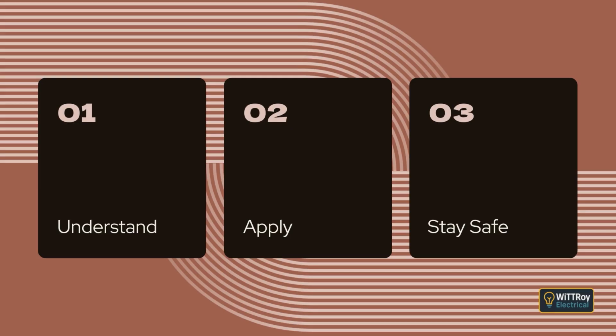Utilization voltage is the voltage that actually arrives at the equipment. The installation must be designed so that, during normal operation, the voltage at each appliance or item of equipment is suitable for that equipment. To achieve this, the designer must consider voltage drop along the cables, the length of the cable runs, the loading on the circuits, and the supply tolerances discussed earlier. The standard refers to Clause 3.6 for the detailed voltage drop limits.